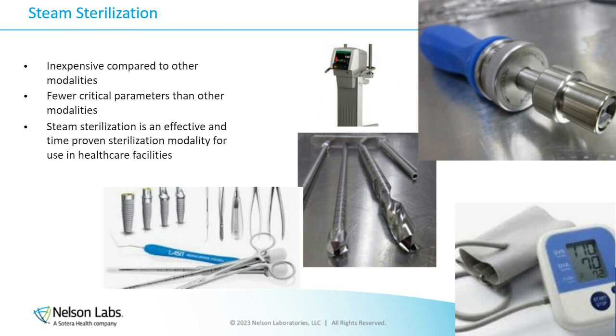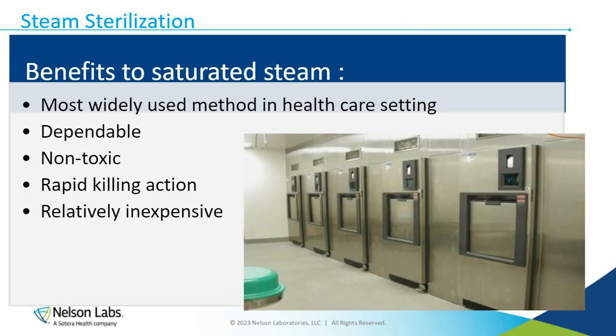So why is steam sterilization so popular in healthcare facilities? It's inexpensive compared to other modalities. There are fewer critical parameters than other modalities, so it's easier to monitor and to validate. Steam sterilization is also very effective and time-proven, making it a very good modality to use in hospitals and clinics. Benefits include that it's widely used and understood, dependable, non-toxic, has a rapid killing action, and is relatively inexpensive.